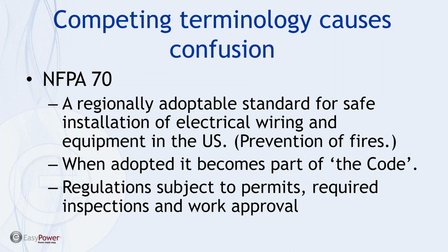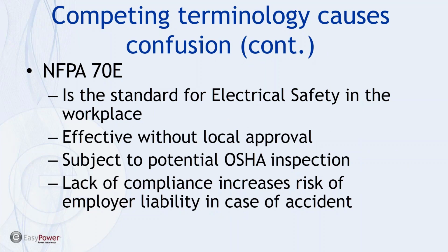NFPA 70 is usually referred to as the National Electric Code, and it's enforced by a series of checks and balances, including permitting, inspections, and approval by certain designated authorities. So yes, it is regionally adopted, and it does have certain articles that can be considered grandfathered, but in the past it has not had all that much bearing on arc flash. To confuse the issue, the standard for electrical safety in the workplace is labeled NFPA 70E, and it's effective at the time it's released. It's not subject to local approval, and it's frequently cited by OSHA when fines are assessed, usually after an event or a problem has been recognized due to employees being hurt or sent to the hospital.